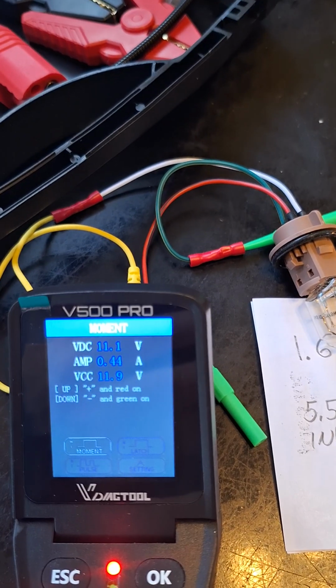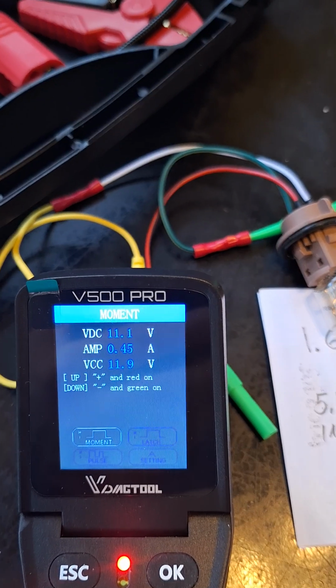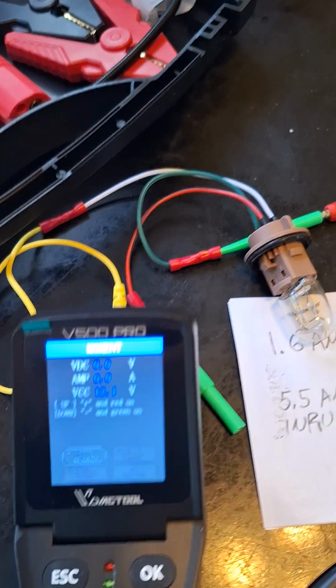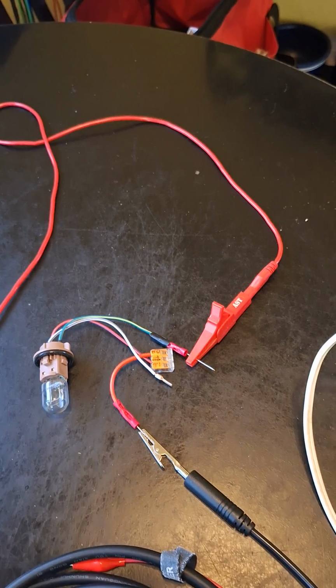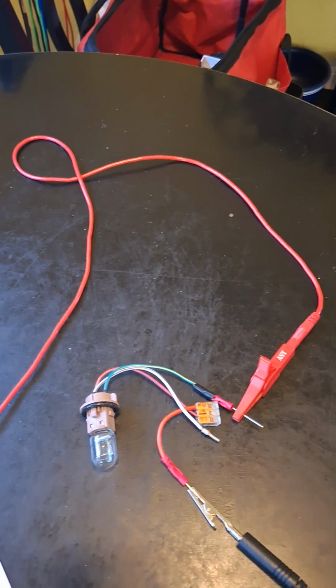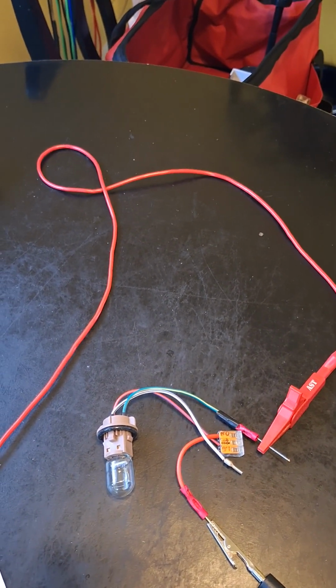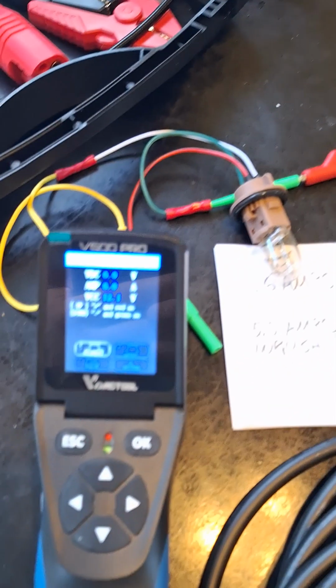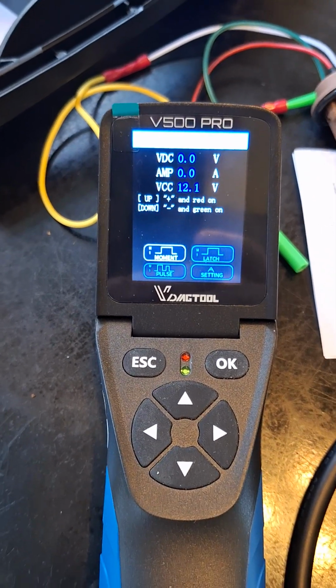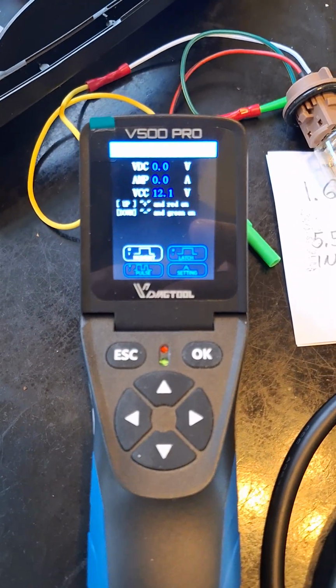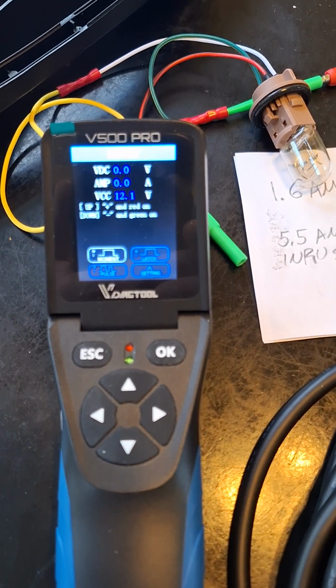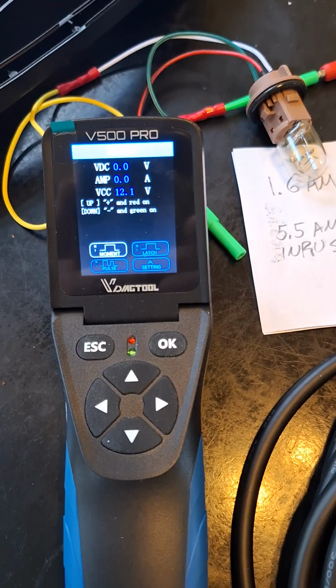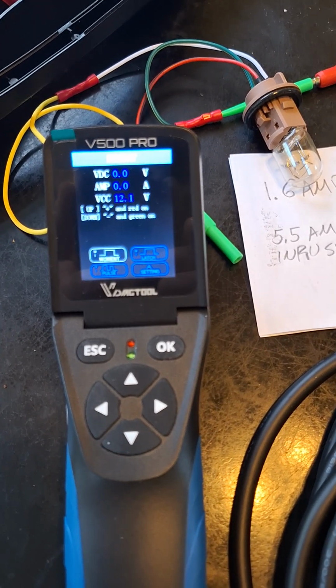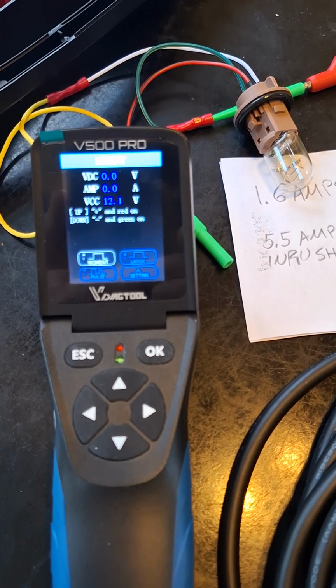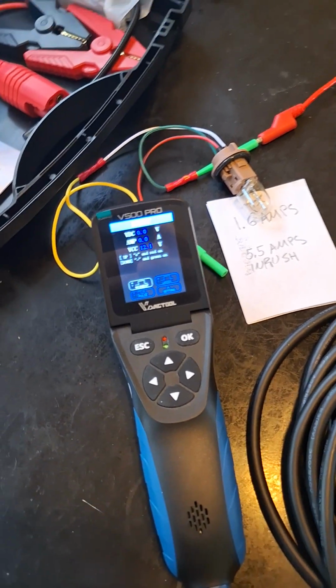So this is not going to trip the breaker, which means that this line is not carrying as much current as it should be able to carry, because it would otherwise trip the breaker. So if you're testing a line that's supposed to carry 10 amps, you can set your breaker to that level and see if it's able to actually carry those amps or not by whether it trips the breaker. I hope that's helpful.